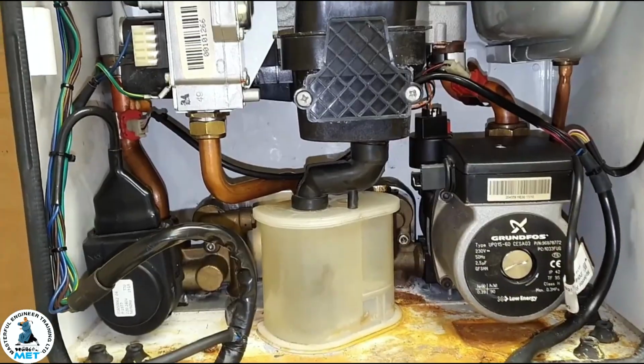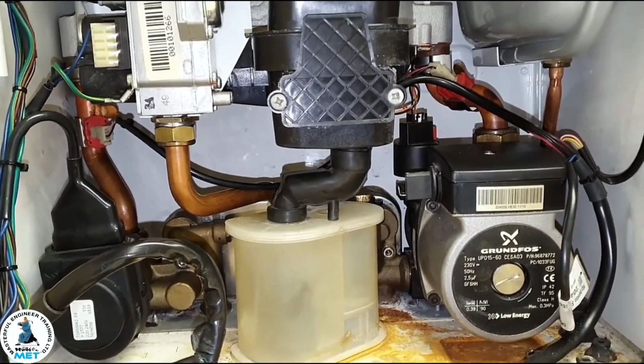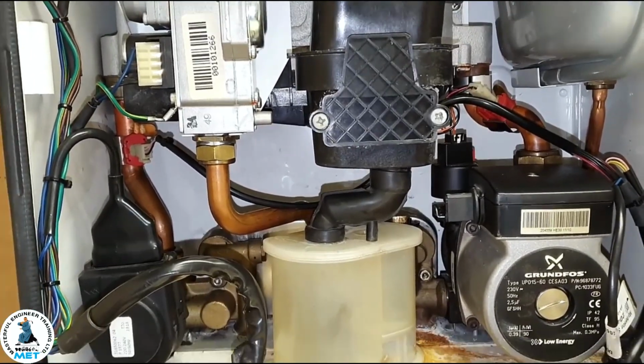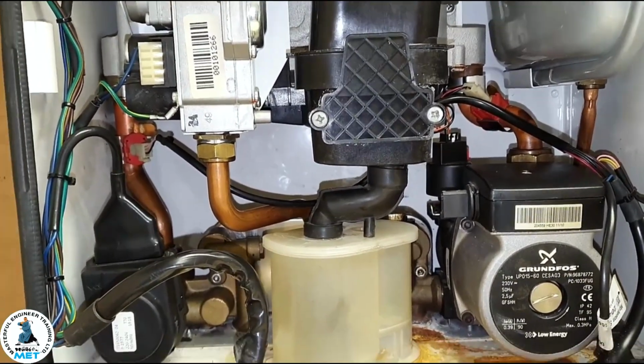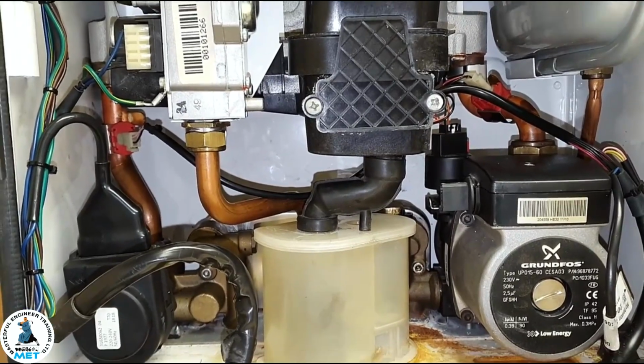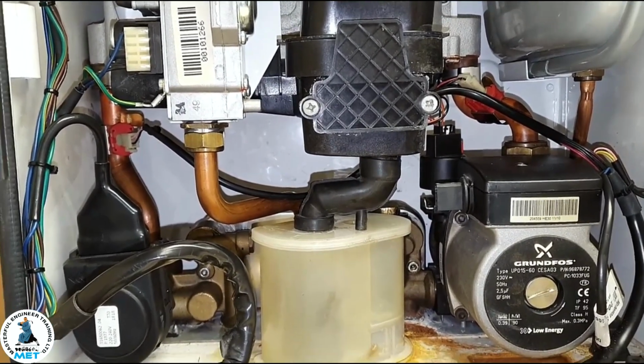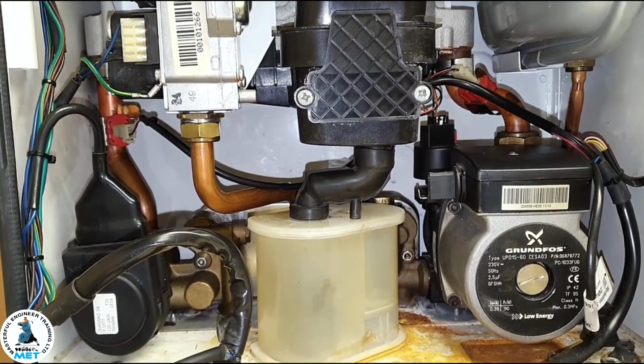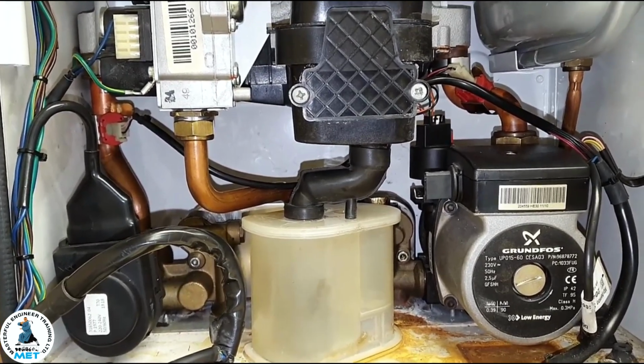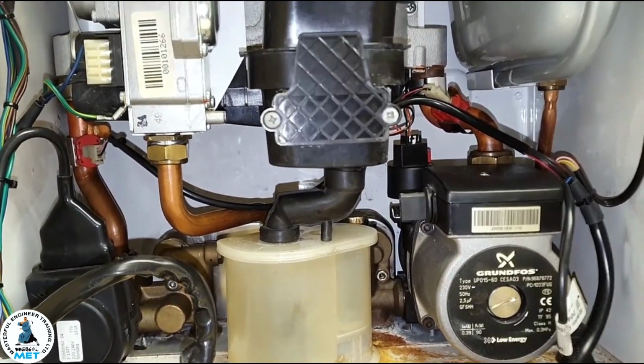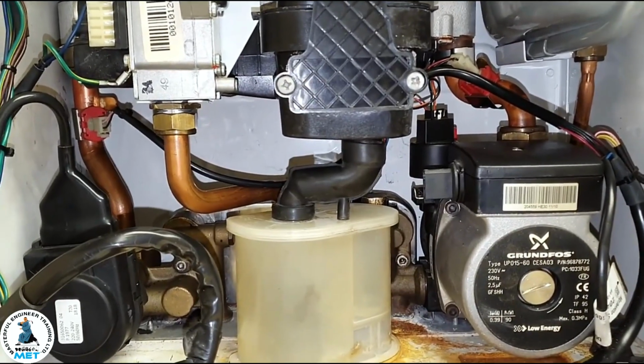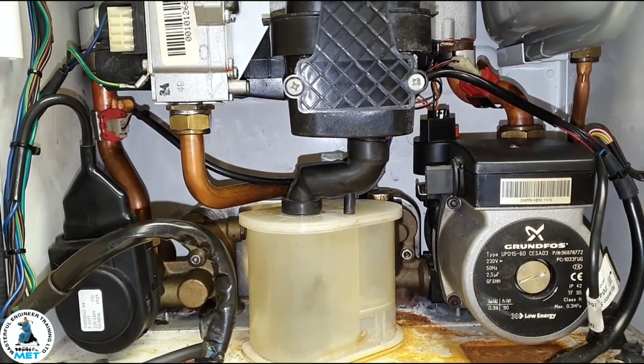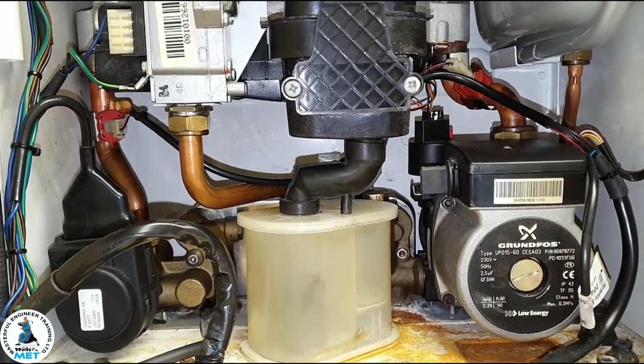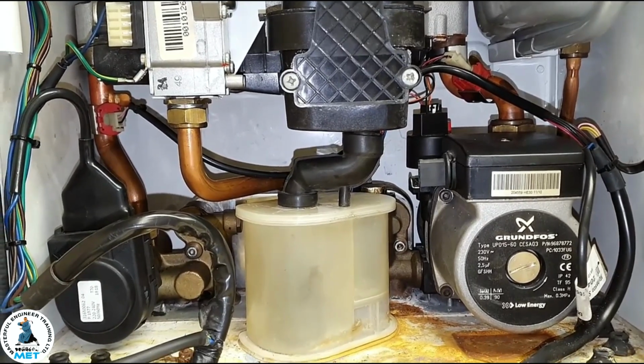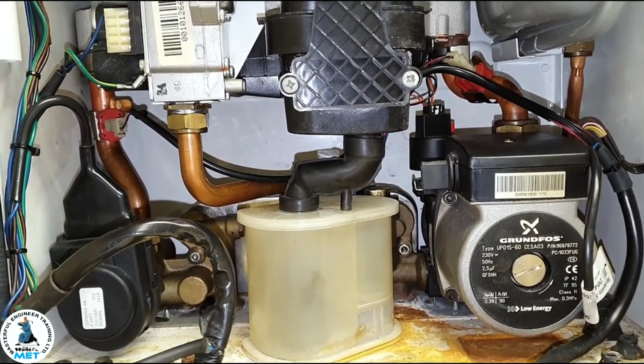Right, you got another question you'd like to ask? Yeah Tony, you got me a wee bit confused here. Just before, I understand the part when the pressure increases when the heating's been on - it's either the vessel that's lost its charge, or failing that, the expansion pipe that's got a blockage in it. But previously, when you said about low water pressure, you also said there could be a blockage in that expansion pipe - why is this?